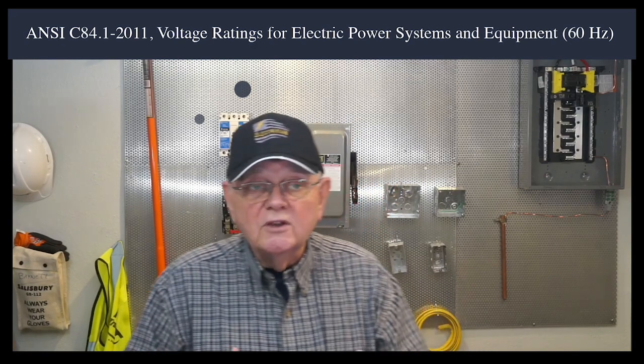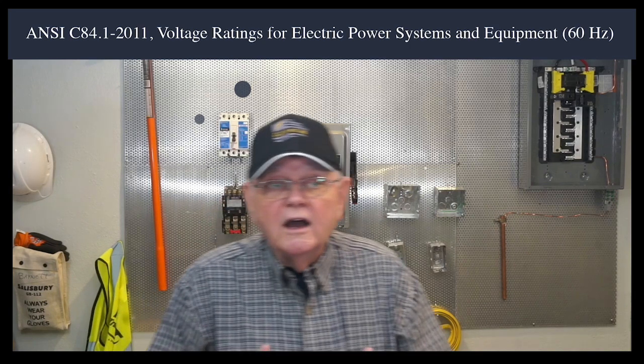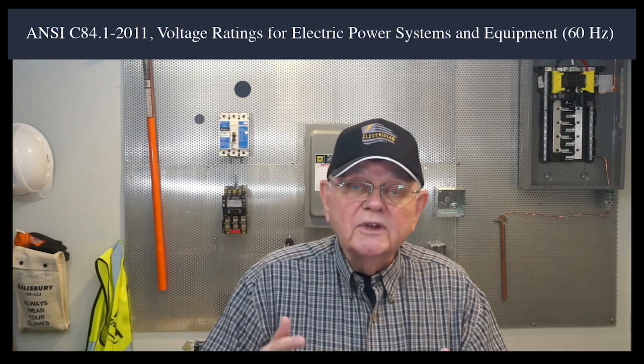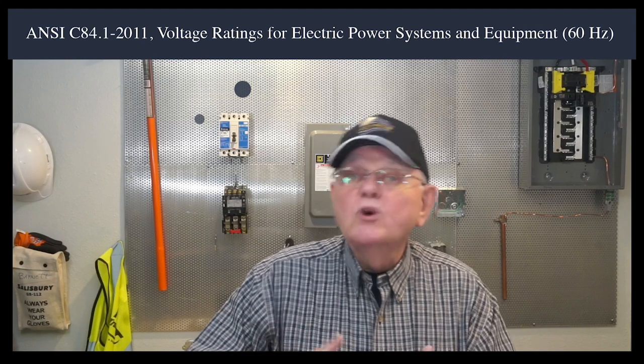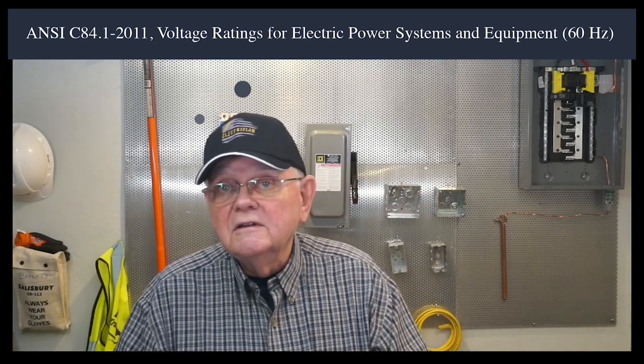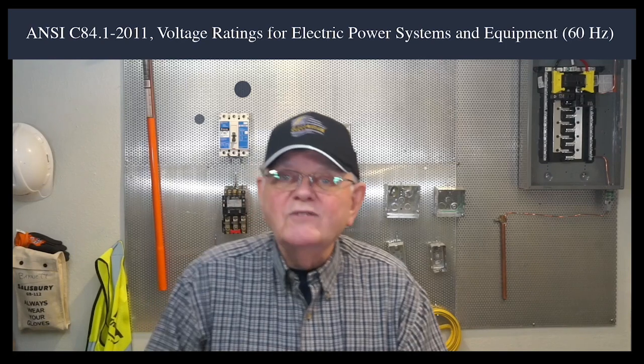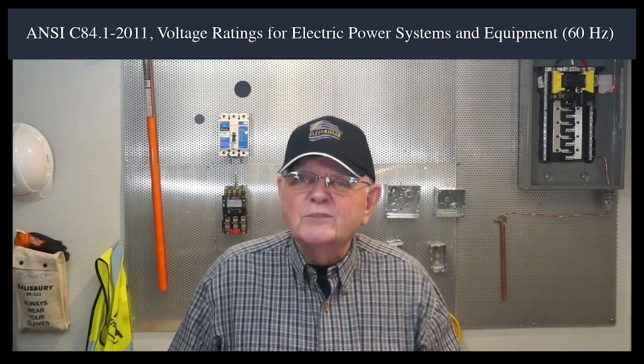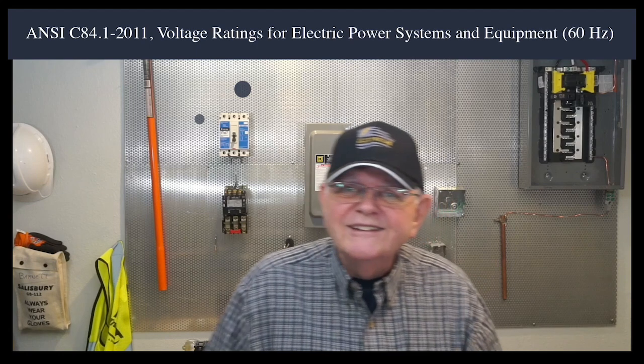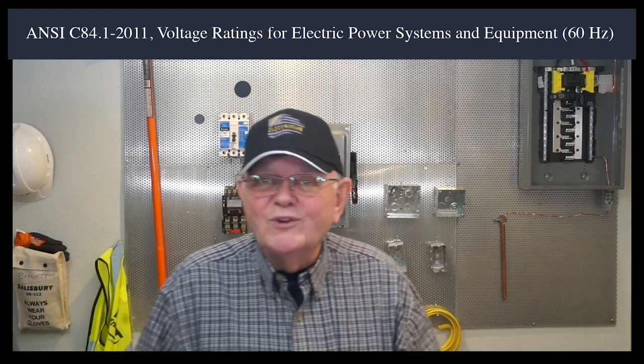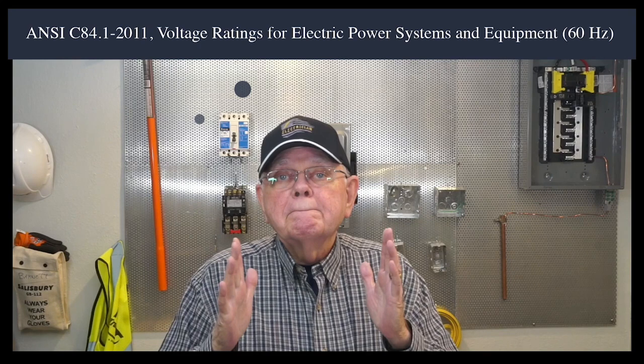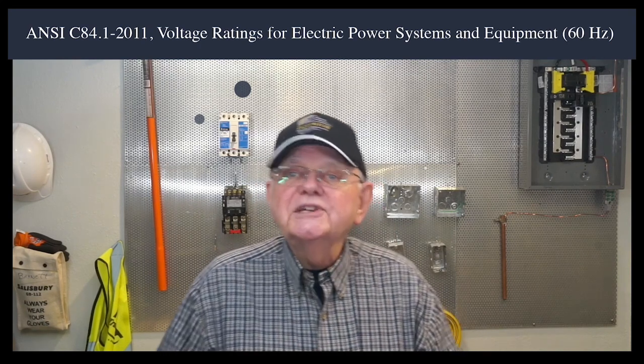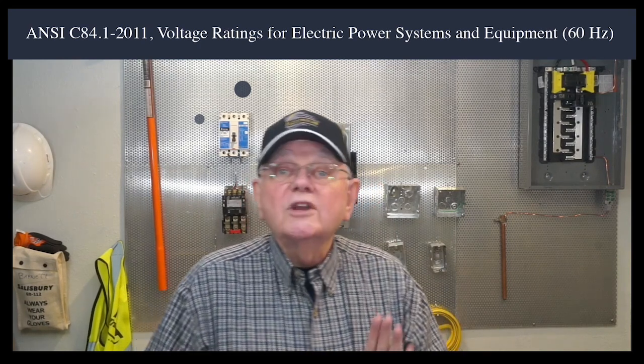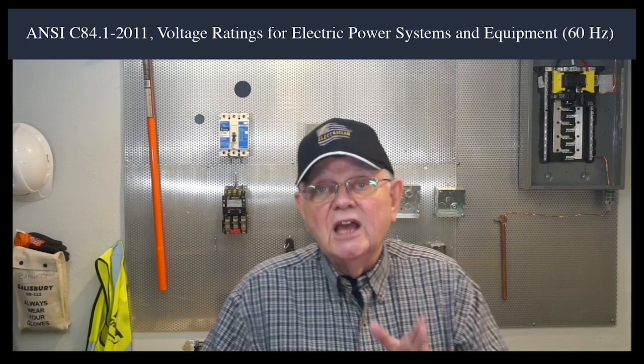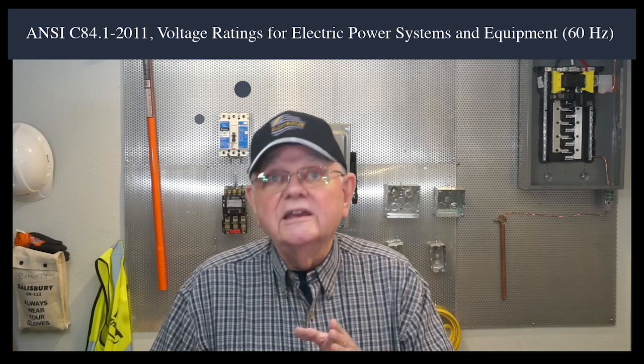So for instance, we could look up and find that according to the IEEE, medium voltage systems go all the way up to 100 kV. However, I can't buy 100 kV metal-clad switchgear to put inside of my building. I don't think it's going to be medium voltage equipment. So you might want to take a look at that ANSI C84 standard if you have any questions about the classifications of the actual voltage level of the systems. You don't find this information in the NEC.